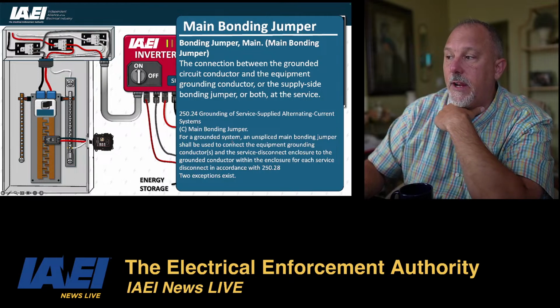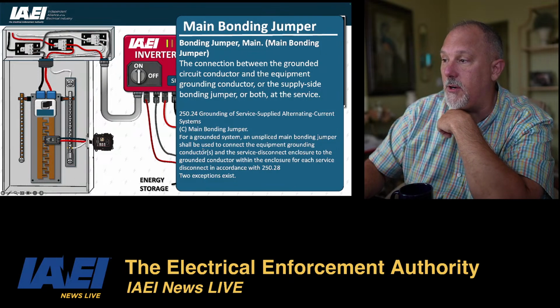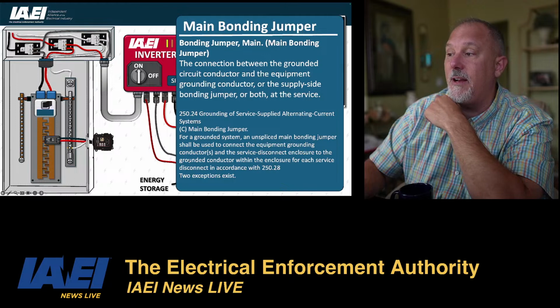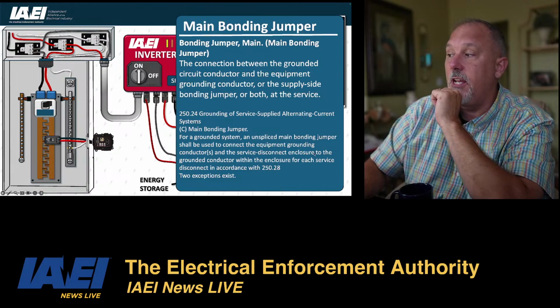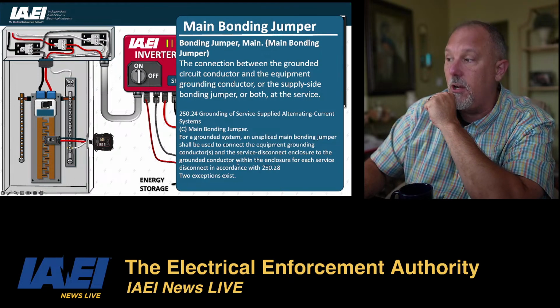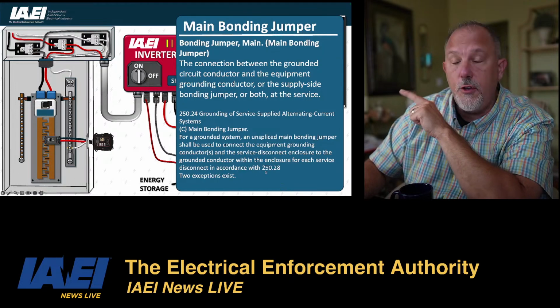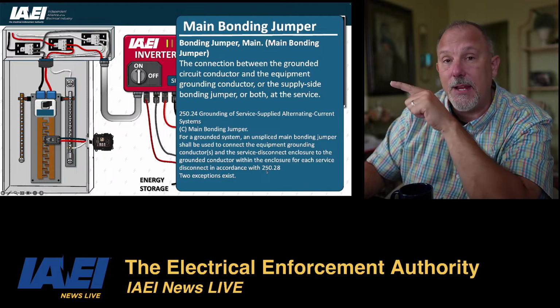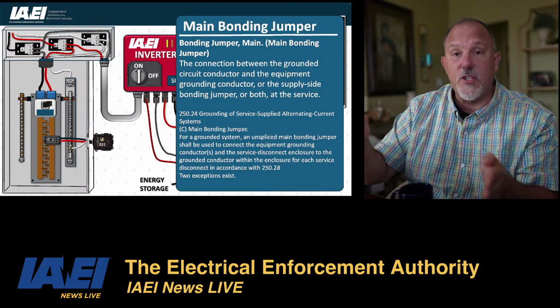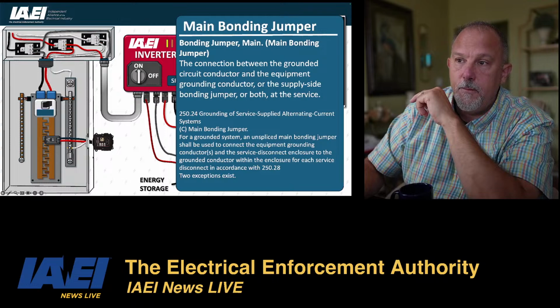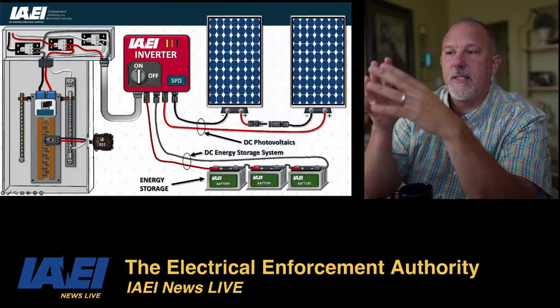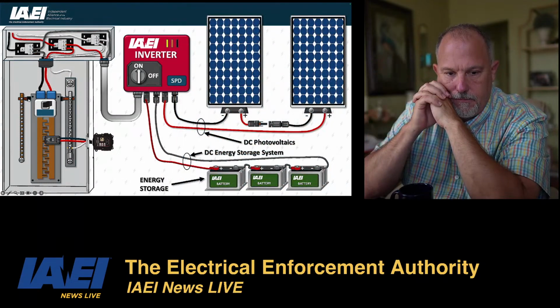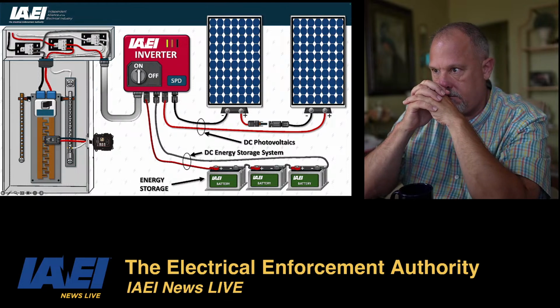250.24(C) says, for a grounded system, an unspliced main bonding jumper shall be used to connect the equipment grounding conductor and the service disconnecting enclosure to the grounded conductor within the enclosure for each service disconnect in accordance with 250.28. And 250.28 is going to tell you what is permitted and what's not permitted. Okay, so that's that portion of the system.